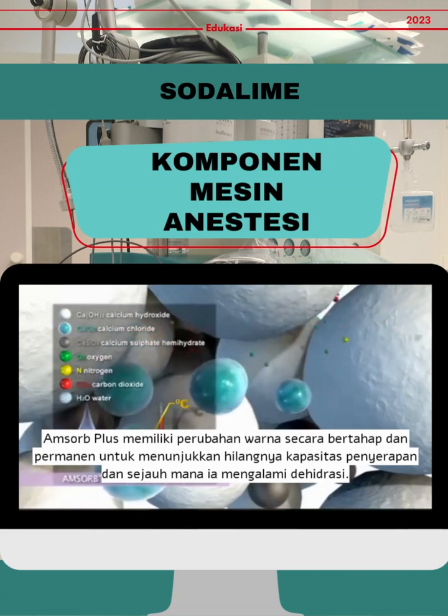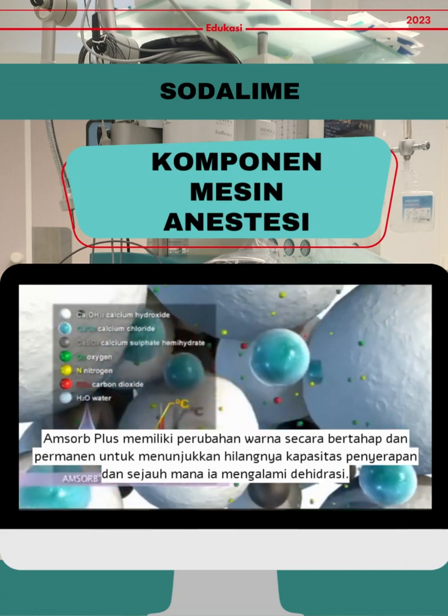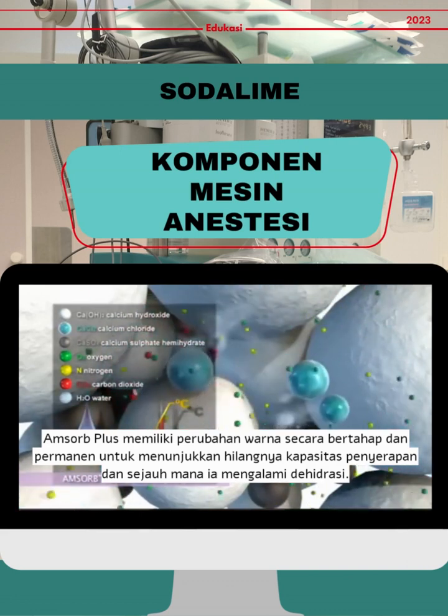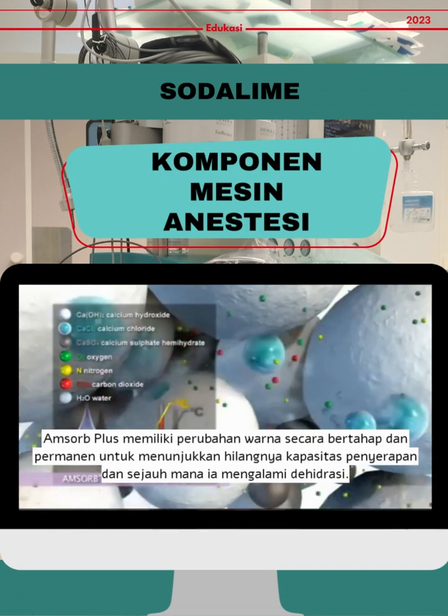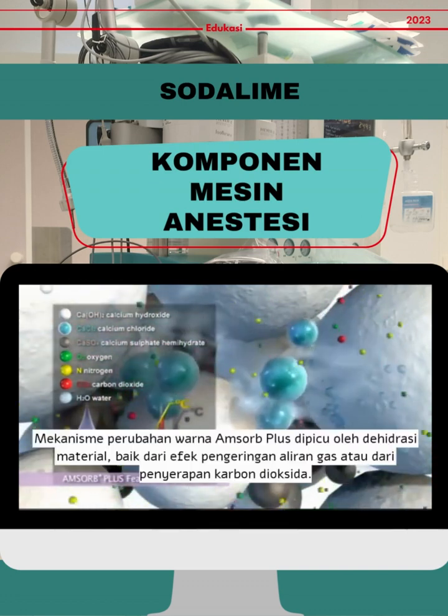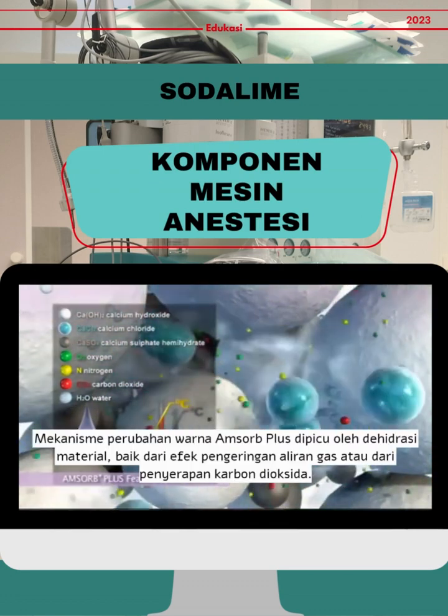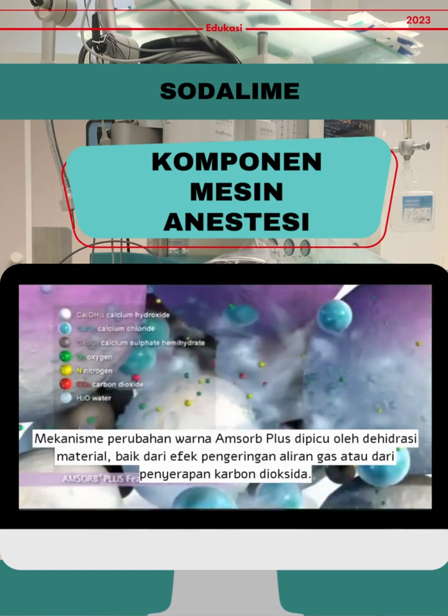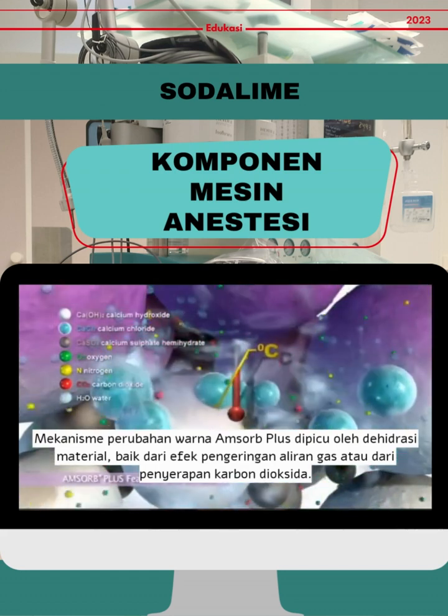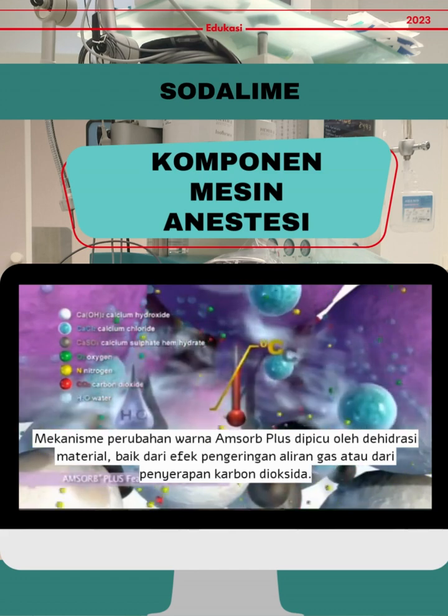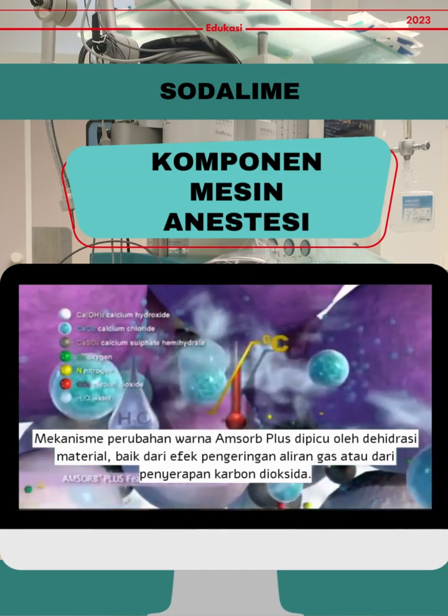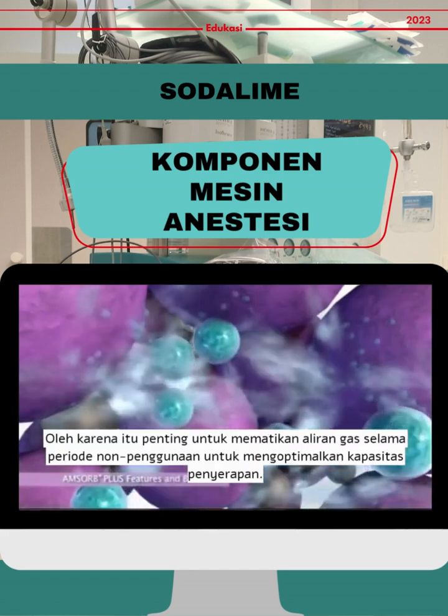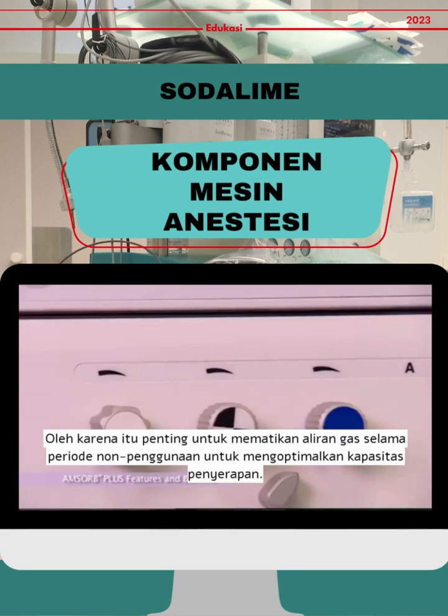Amsorb Plus has a gradual and permanent color change to indicate loss of absorption capacity and the extent to which it has become dehydrated. The color change mechanism of Amsorb Plus is triggered by dehydration of the material, either from the drying effects of gas flow or from carbon dioxide absorption. It's therefore important to switch off gas flow during periods of non-use to optimize the absorption capacity.